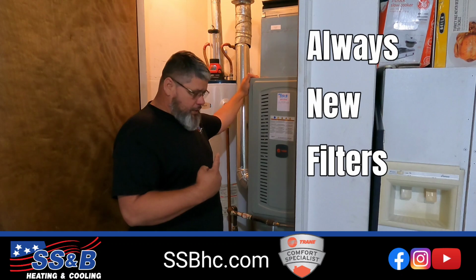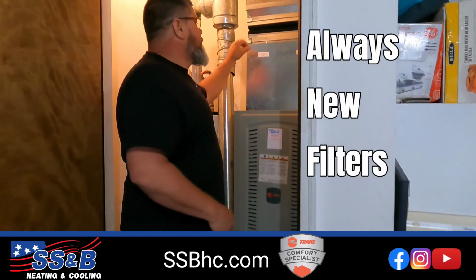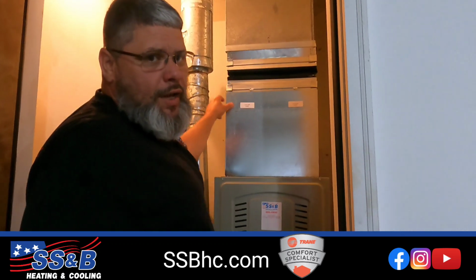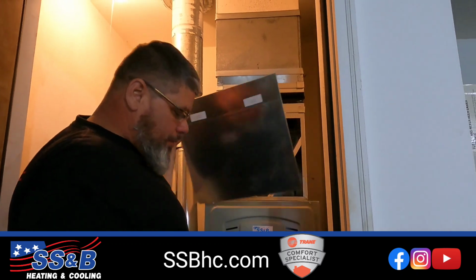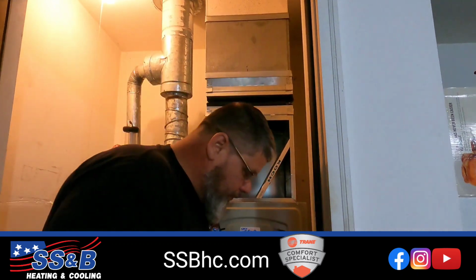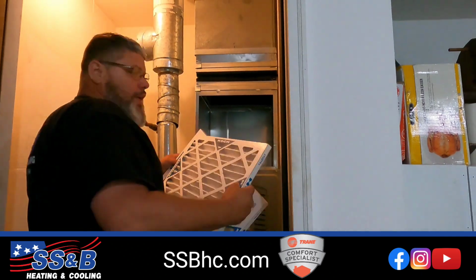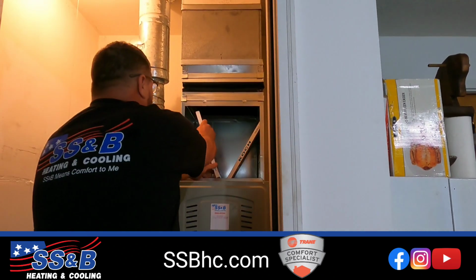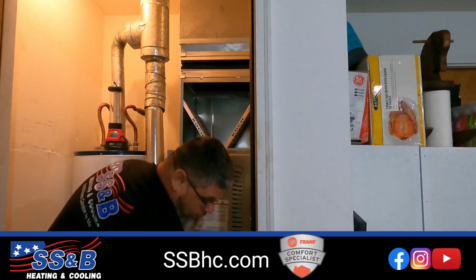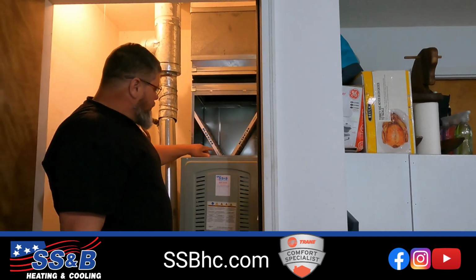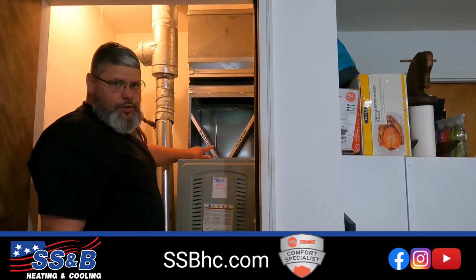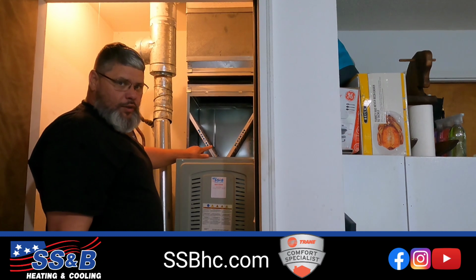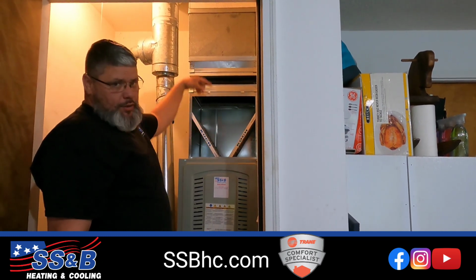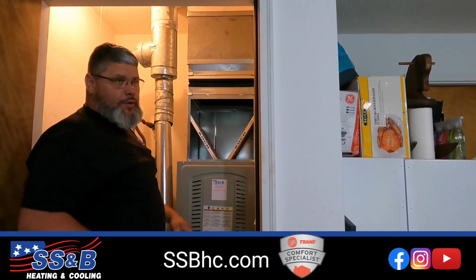One thing is we change filters on all the systems. This one actually has a filter rack inside above the furnace. On your filters, you always want to make sure that your arrow is facing with the airflow, which in this case would be going this way, so make sure the arrows are going the right way. Go ahead and get started.